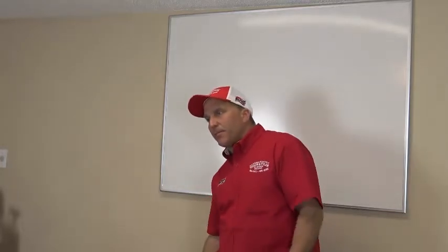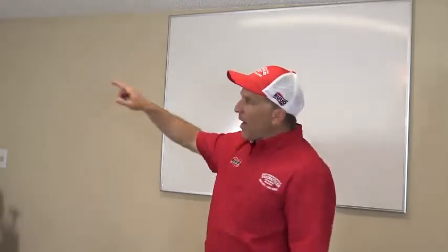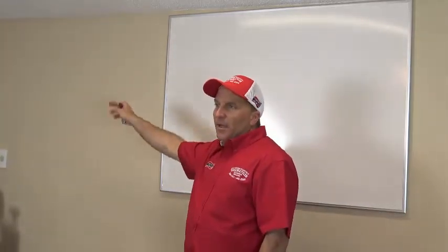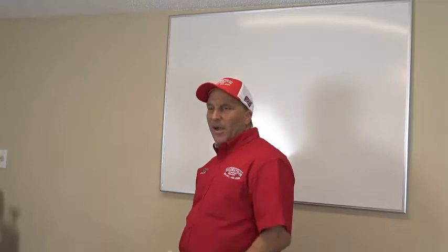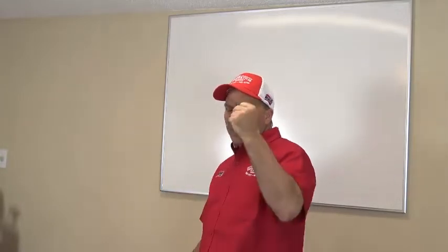So here's what I want you to do. I want you to run that system right now. And I want 24 volts going to my contactor. And I want the power to go out outside. And when the power goes out, what's going to happen to the contactor? It's going to open up, right? Now, what happens when that power comes right back on half a second later? Boom, comes right back on, and that compressor is running, it stops, and it starts again, right?